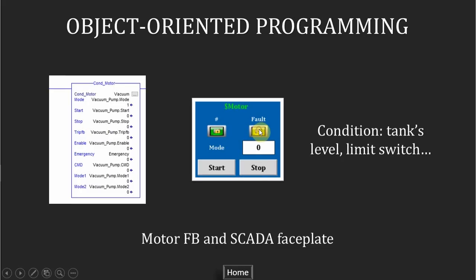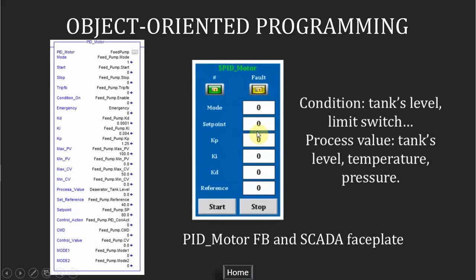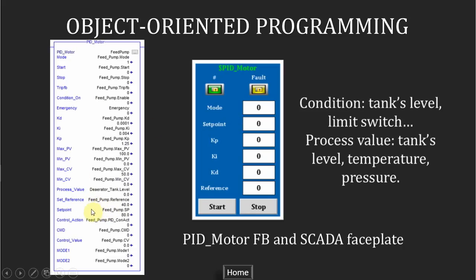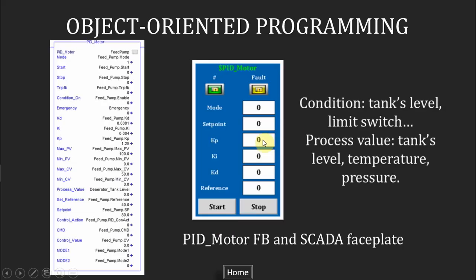The second one is the PID motor. The difference between these two functions is the PID controller. The controller will compare the set point to the process value. This is the process value. And it will compute the output signal, the control variable here. It will change the speed of the pump or the open duty of the valve. An operator can change the PID parameter online to optimize the response of the device.